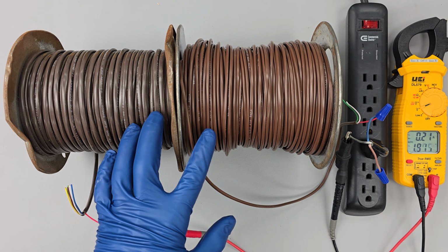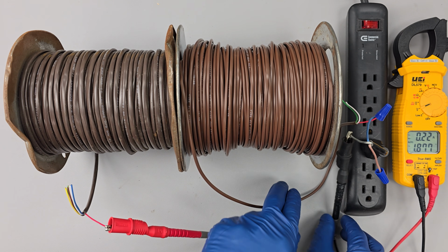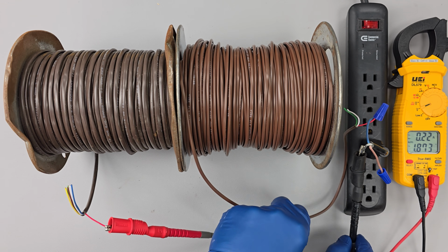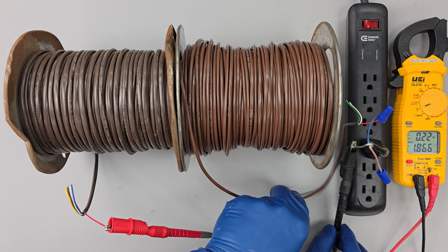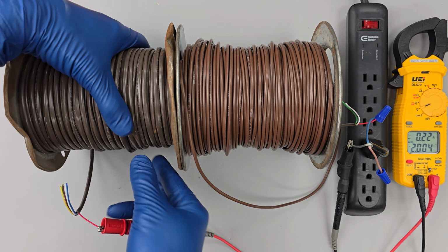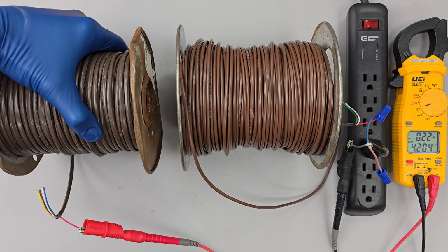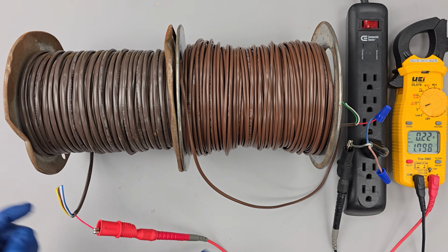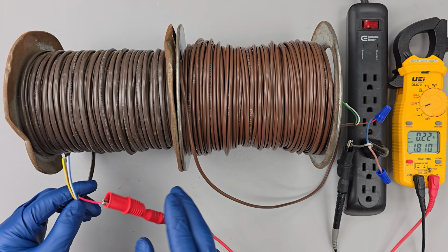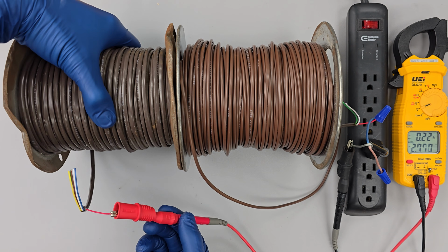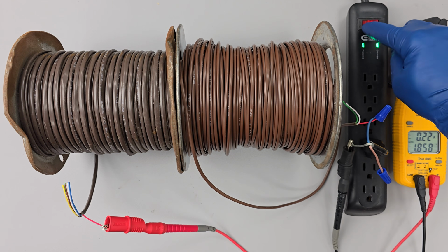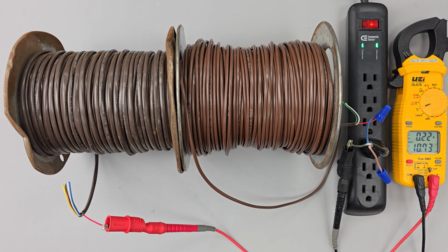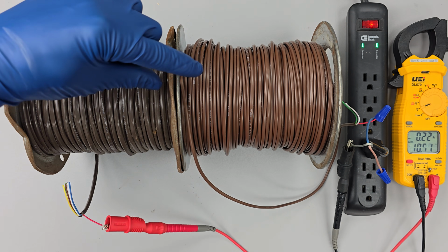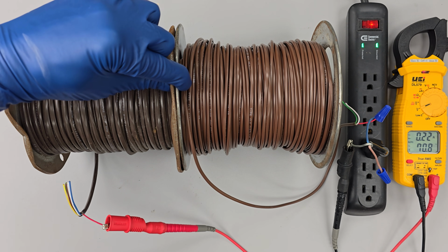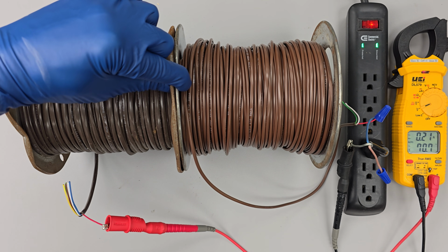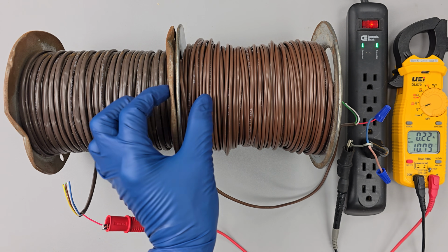Now we have 2 spools of thermostat wire next to each other. And so we have our alligator clip on the common, and we have one of the wires being hot. The other side is not connected to anything at all. It's just up fairly close to it. And then on this one, we have a red wire that's just on this spool right here. And so we're going to turn the power on and measure for voltage. And so you can see right here, we're measuring 10.7 volts. And if I help connect the metal a little bit more, right here, you see 10.7. And so it's a little odd, right?